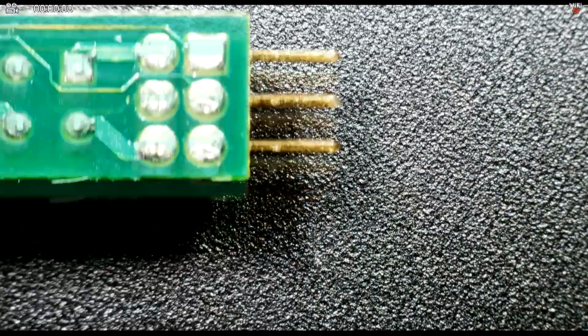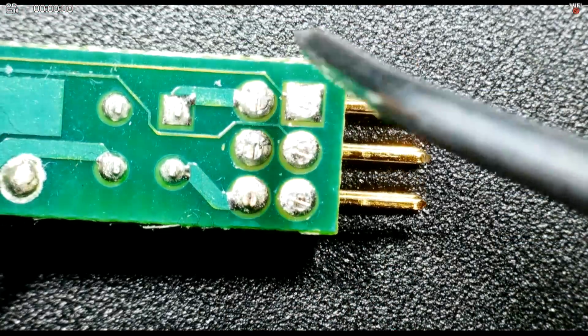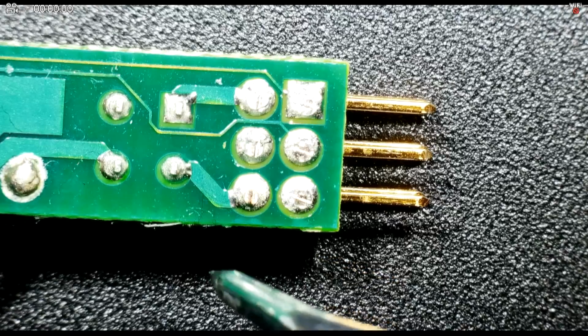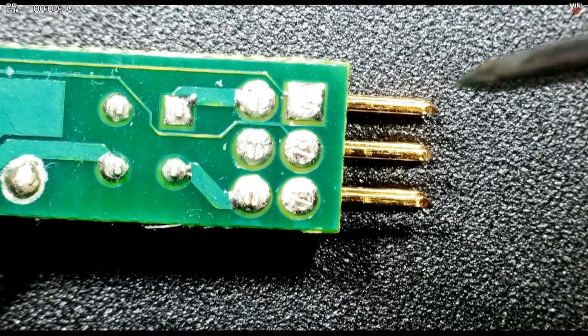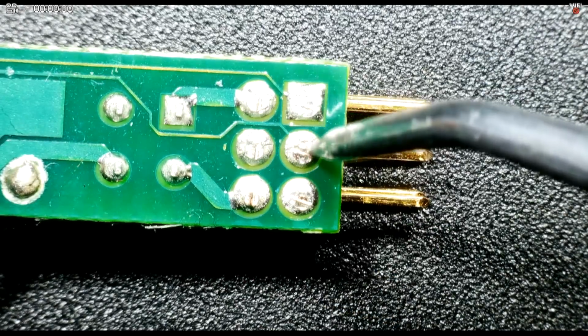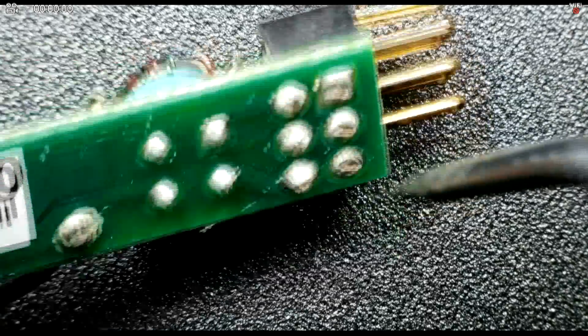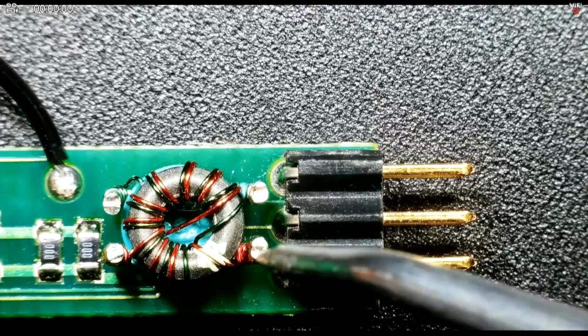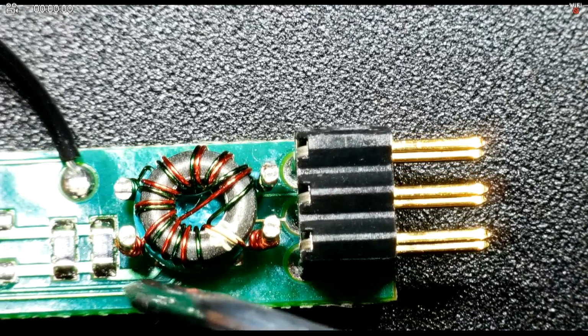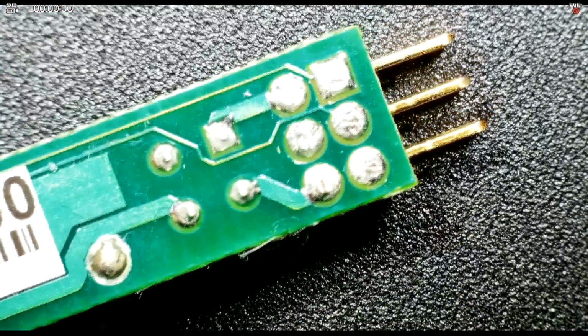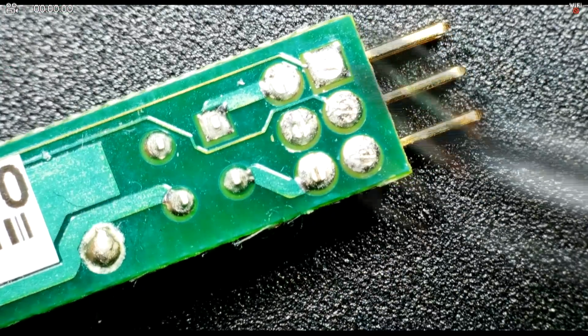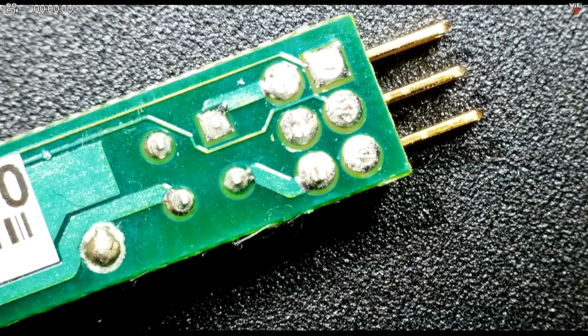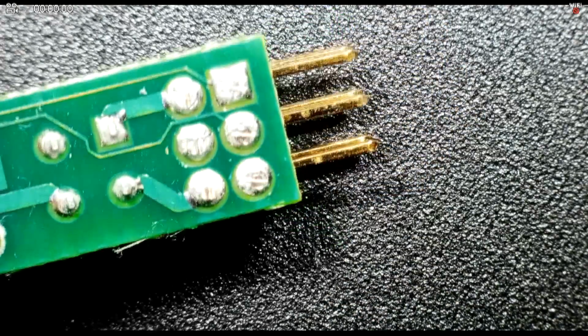Now if I flip this to the other side, in order to get some estimate of what the pinouts look like, you can see that we have two thicker traces here. I believe these are going to the transformer inside of the transformer head, and then we have four other pins, two of these with two thin lines coming out of them, and if I flip it to the other side, the other two have another two thin lines coming over there. So all of these must be to power the Hall effect sensor, as well as have the data from the Hall effect sensor go back into the probe head itself. So all these signals need to go back and forth, and then when this thing is assembled, you just basically plug them in like that.